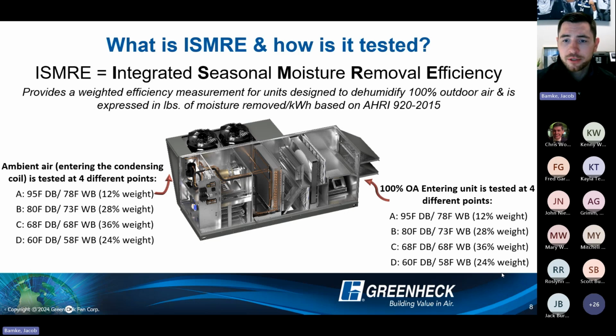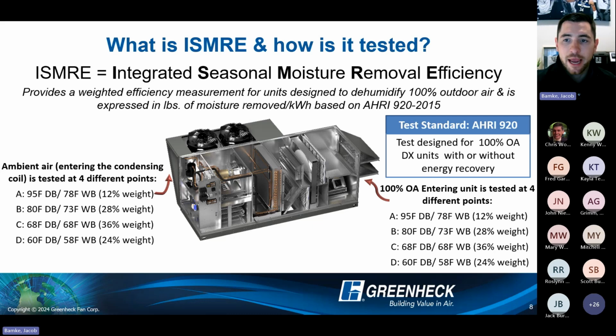And then one other thing you'll see with this is the weights change as well. A little bit more geared towards full capacity days, just because you're designing more of your DOAS equipment for those full capacity days. However, still only 12% is your full load day. And this is test standard AHRI 920. And again, this was really laid out to focus truly on those 100% outside air systems.